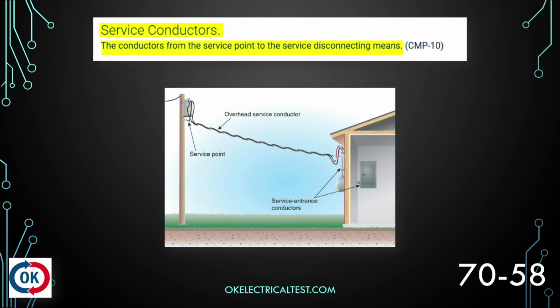Let's go to letter S. We're going to go to page 58. Page 58, service conductors. Again, we all know what the service conductors are, but let's see what the code defines those as. That's our conductors from the service point to the service disconnecting means. So here in this illustration, from our service point, which would be that transformer, right, to basically our weatherhead and down to and including the meter there, that is going to be our service entrance conductors. Also from that meter to that service disconnecting means, that would also be service conductors. So when we're sizing our service conductors, that's what we're talking about.